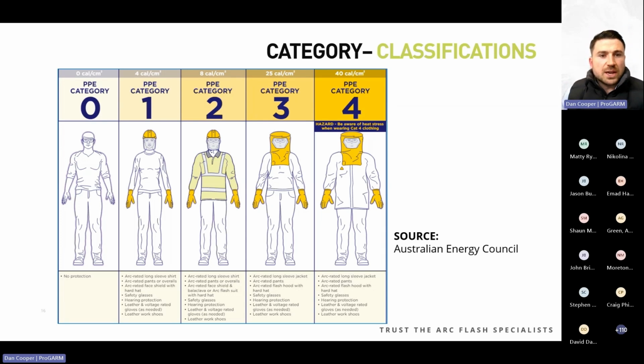You can achieve specific cal ratings by adding layers of protection, but the only way to get the correct level of protection when garments are layered is if they are tested and certified together. More on layering and how to add levels of protection to ensure everyone is safe for the tasks they need to do will come shortly.